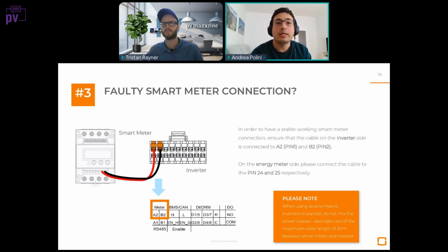Also, you need to take care about the distance between the energy meter and the inverter. It could be that the energy meter is actually quite far from the inverter because of the location of the installation of the distribution box of the house. The RS485 communication protocol can work theoretically up to 100 meters of distance. However, we are recommending to use less than 20 meters of cable between our inverter and the smart meter.